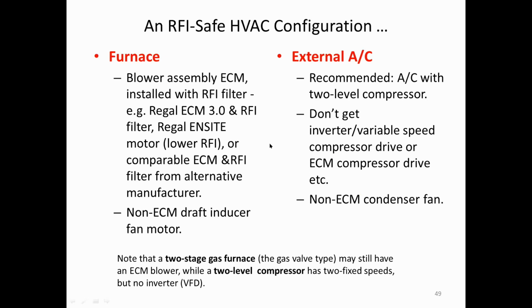Here is a safe configuration, RFI safe configuration. In the furnace, you know you're going to have an ECM, but I would try to get one from a manufacturer, Regal being one, but there are many manufacturers that make ECMs, or a comparable ECM, and try to get an RFI filter from the manufacturer, not necessarily the alternative manufacturer. I would also insist on getting a non-ECM draft inducer fan motor. There is no reason to have an ECM inducer for the fan motor other than reasons of efficiency.